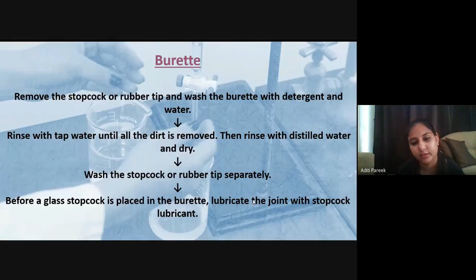Burettes. One important thing to keep in mind before we clean volumetric glassware such as burettes or volumetric flasks is that we should never use inappropriate brushes, because these brushes can scratch the glassware and can cause an error in the calibration of that particular glassware. So for the cleaning of a burette, we have to disassemble it. For that, we have to remove the stopcock or the rubber tip and wash the burette, as we have already discussed, with the soapy detergent, then with water, and then with distilled water to remove all the dirt or contaminating materials. And we should also wash the stopcock or rubber tips separately, and before assembling them we can lubricate the joint.